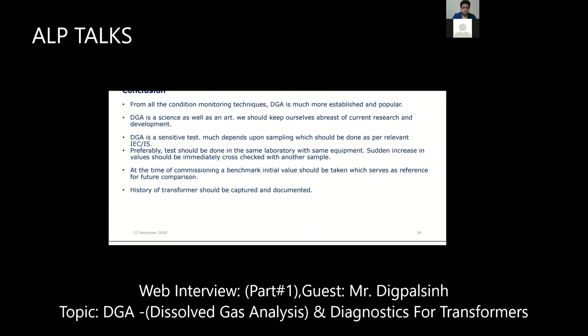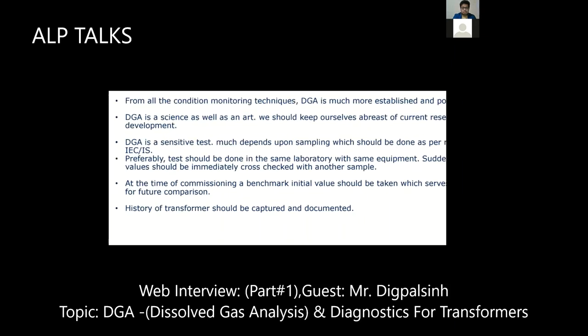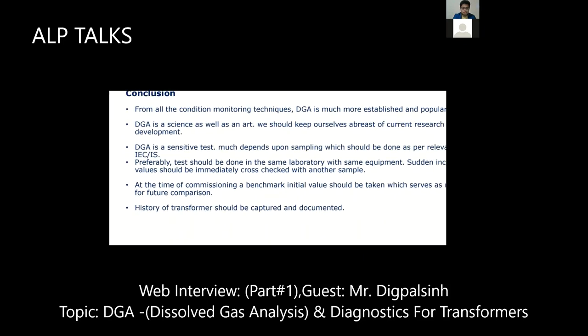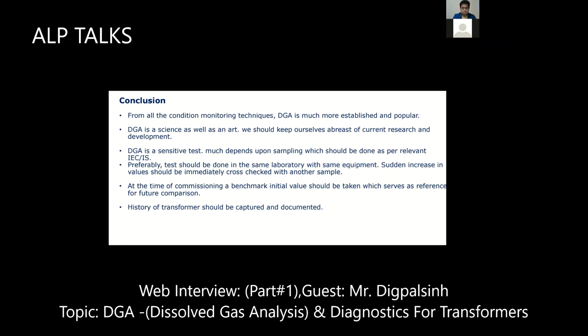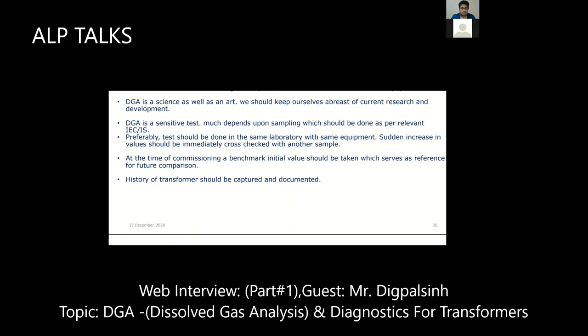The third point is that if you do one analysis and after 6 months you go with CPRI, then DGA is not useful. It is a very sensitive test. If you're going with ADA or PGCL or any other laboratory, you have to follow only one laboratory. Usually, tests will be done in the same laboratory with the same equipment. DGA equipment should be the same for every 3 or 6 month interval, and the lab will also be the same, because it may not be consistent if we change it. Exactly. And the people taking the oil should also be experienced.